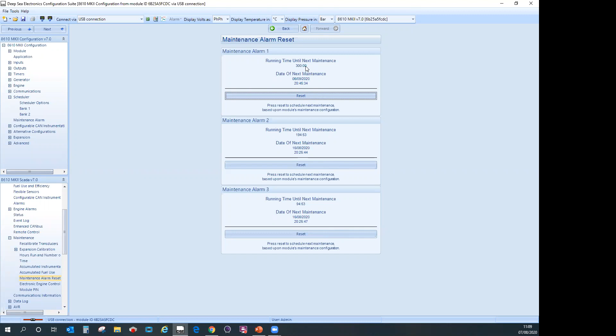Another section of SCADA which I'd like to show you, which we get a lot of calls about: you can put a PIN code on the module, and that PIN code will stop the customer or end user making any changes to the controller without having access to the PIN code. Very common feature. So this means only authorized people can go to site and make changes. The thing to make you aware of is if you put a PIN code on there and you forget the PIN code, we at Deepsea have no way of knowing what the PIN code will be, and there is no way of resetting the PIN code unless you return the controller to us. Okay, so you must return the controller to us. If you've forgotten the PIN code, it's going to have to come back, and we actually have to desolder some items on the back of the controller and replace them to reset the PIN code. So it's not an easy task. So please, if you're going to put a PIN code in it, make sure you remember it, or make a note of it in a safe location.